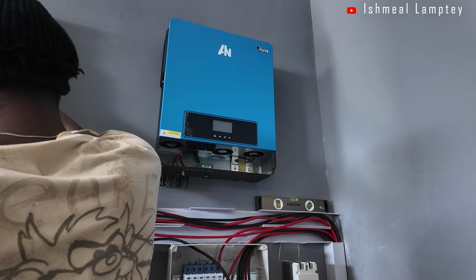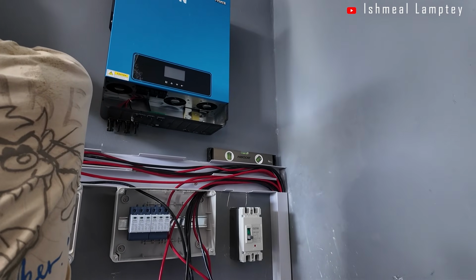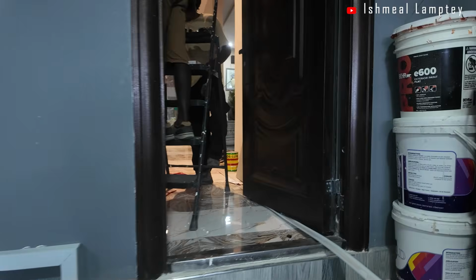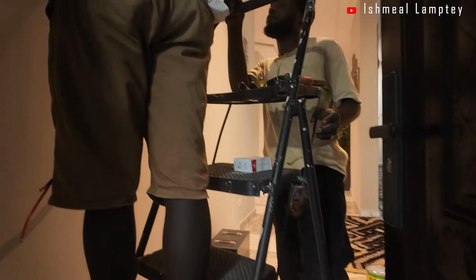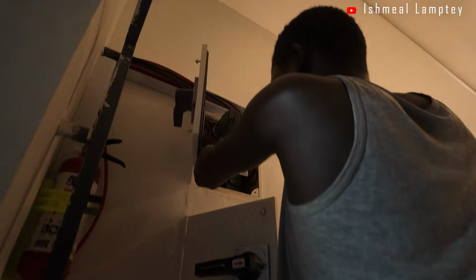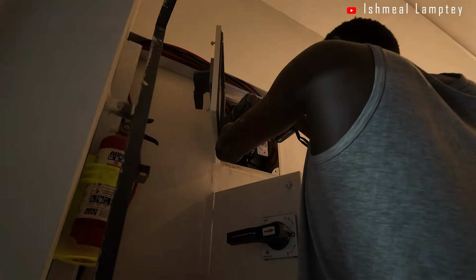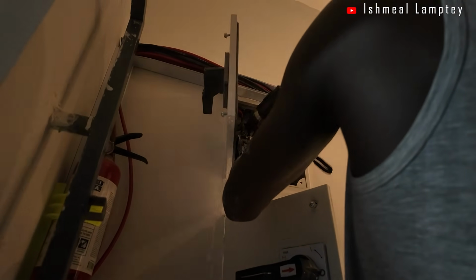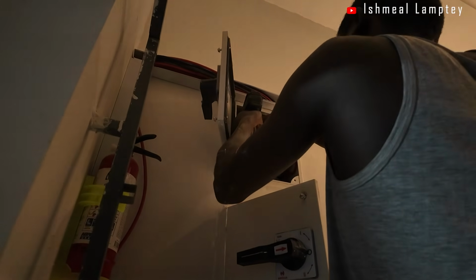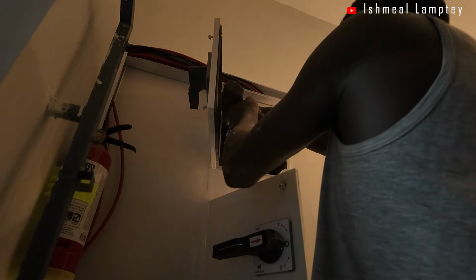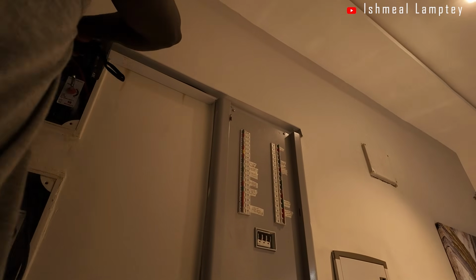One interesting thing was that the house was using a 3-phase system from the grid, but we had a 2-phase inverter to work with. There are a couple of ways to go about installing that, but what we decided, since we had a 2-phase system, was to switch the house from a 3-phase system to a 2-phase system. Prior to that, we consulted the owner, and he confirmed he wasn't even utilizing the 3-phase system he had, so that wasn't going to be a problem. That meant the 3 or 4 cables coming from the grid — we have 3 live lines and 1 neutral.